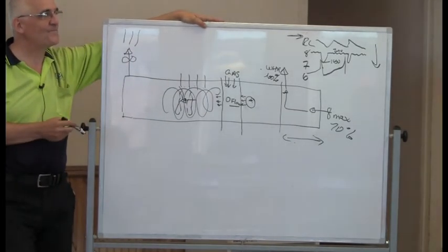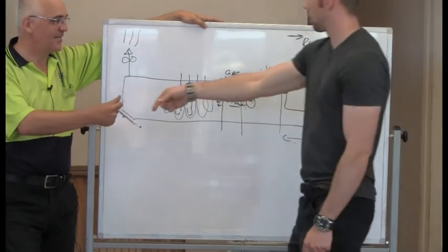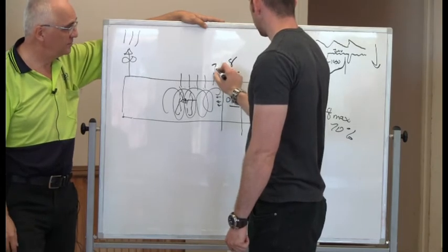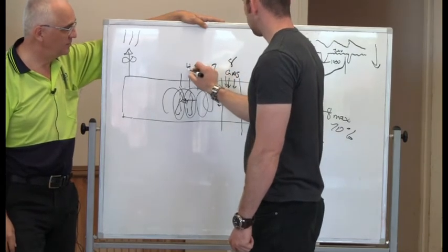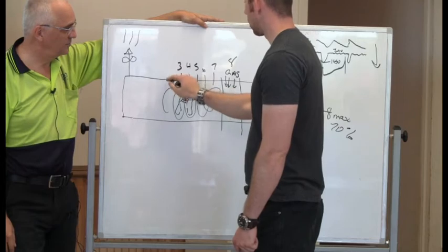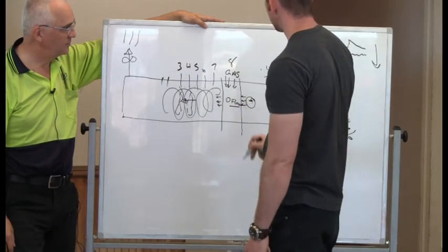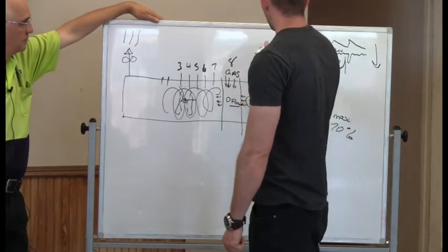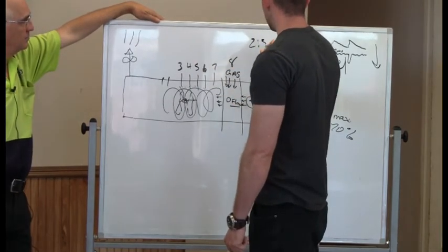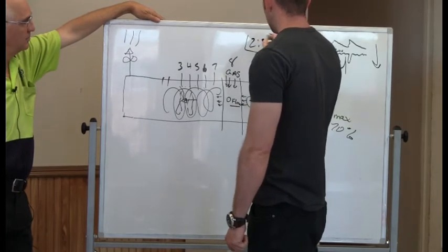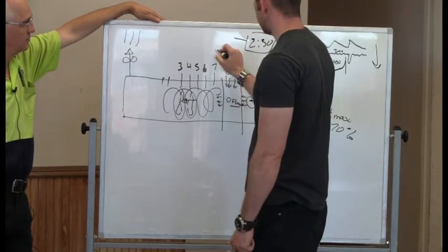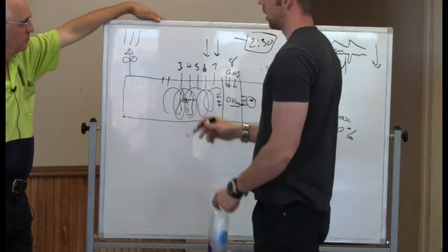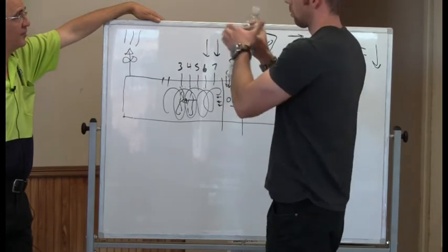In theory, going back to this, if we're flashing here in 8, and then we call that 7, 6, 5, 4, 3, and then you've got the burner groups here that stay on. If I was to write a bit in the PLC that says, when I'm in that 2-minute and 30-second flash time, then cut off the fuel at 7, cut off the fuel at 6, and you have it roll and force the air through.